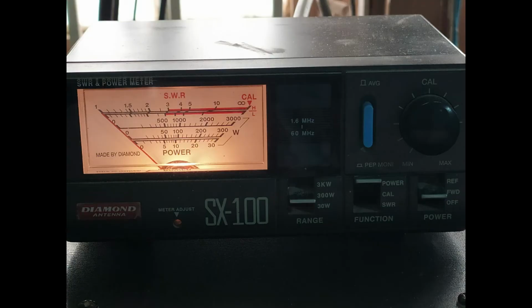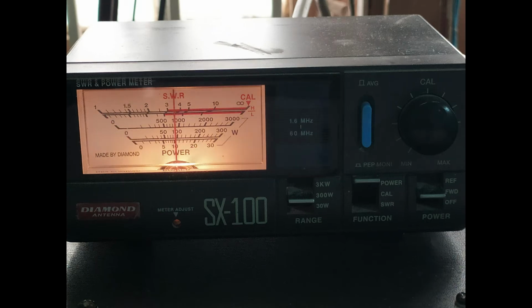When the third selector switch, that is power switch, is in off position, it turns off the display light and meter so it would not give RF power output readings. In order to measure RF power output, the power switch is to be in forward position. The function switch is to be in power position and the range switch is to be kept in appropriate position.